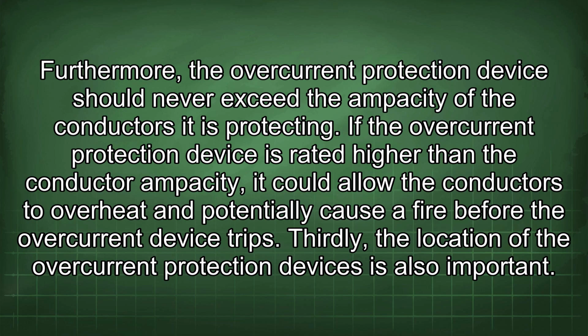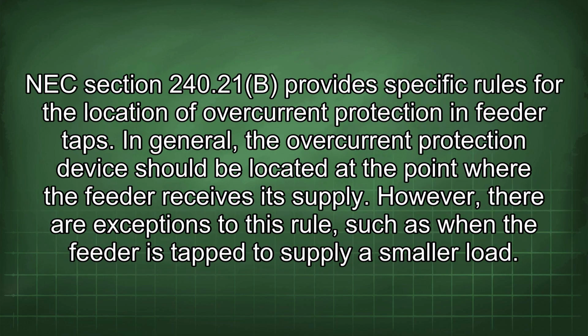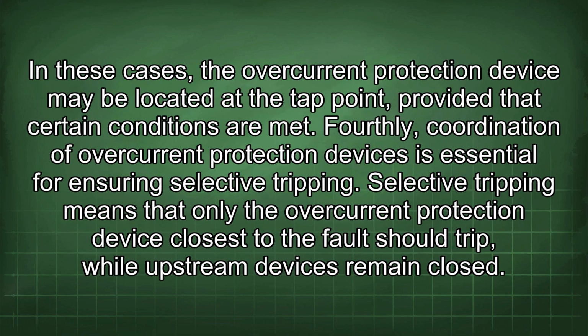Thirdly, the location of the overcurrent protection devices is also important. NEC Section 240.21(B) provides specific rules for the location of overcurrent protection in feeder taps. In general, the overcurrent protection device should be located at the point where the feeder receives its supply. However, there are exceptions to this rule, such as when the feeder is tapped to supply a smaller load. In these cases, the overcurrent protection device may be located at the tap point, provided that certain conditions are met.